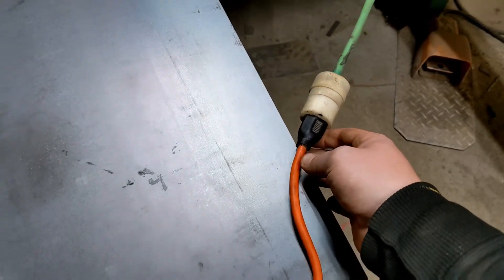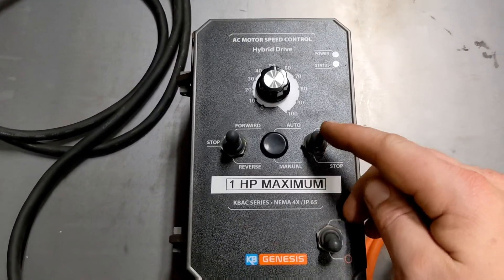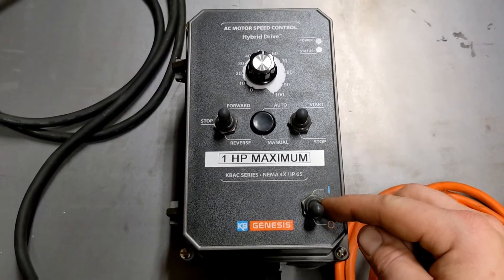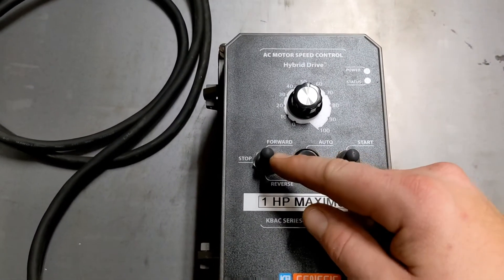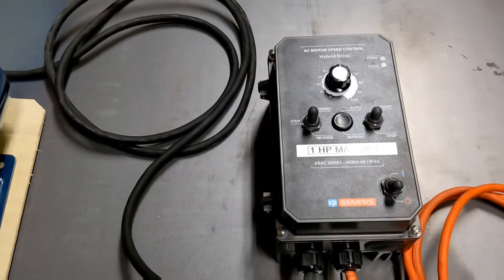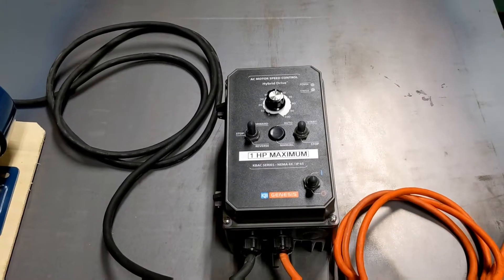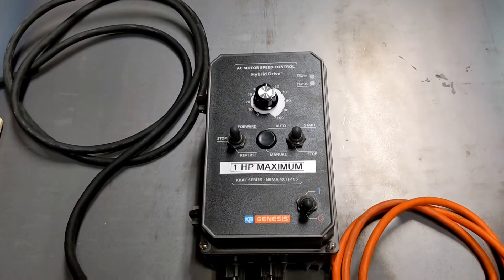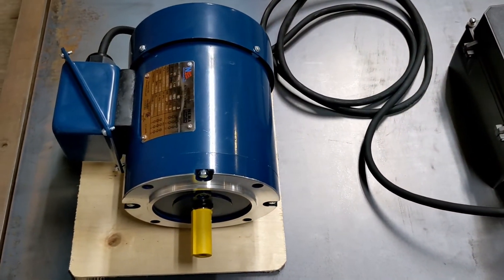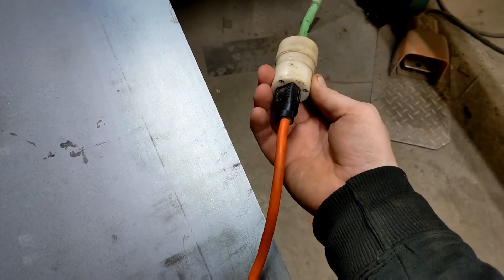You can see it's just in an extension cord. These drives come with the start and stop toggle only, and I've updated this one with the power on and off and the forward stop reverse switch as well. These are all factory options — they just make the unit a little nicer. This particular unit is rated for one horsepower maximum. You can get these KB drives all the way up to three horsepower with the single phase input.